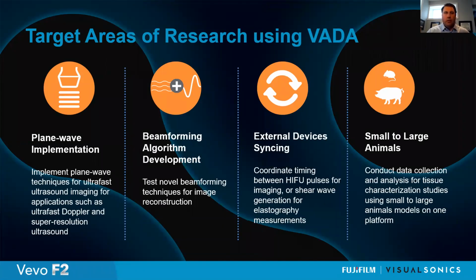So what are some of the things people may want to do using this interface? Well, plane wave implementation I've mentioned several times. This is probably one of the biggest requests that we do hear from users and potential users of our instruments. Here we're looking at typically ultra-fast imaging techniques, where we are firing all elements simultaneously, creating that plane wave. That's what allows us to get up to those ultra-fast frame rates that I mentioned earlier on, upwards of 50,000 frames per second. So some of these techniques allow applications such as Ultrafast Doppler, super resolution ultrasound, and other techniques that are new and emerging modes of acquisition in the ultrasound field today.